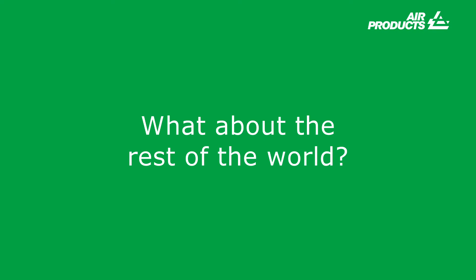So what about the rest of the world? There are many European and international regulations that follow the same theme. If you are outside Europe you will almost certainly find that your country subscribes to these key health and safety measures. Data in the public domain shows that on any given day one in every two and a half thousand untested instruments will fail to respond to a dangerous concentration of gas. Sensor performance can degrade and in some cases sensors may fail in an unrevealed mode, or fail to danger.